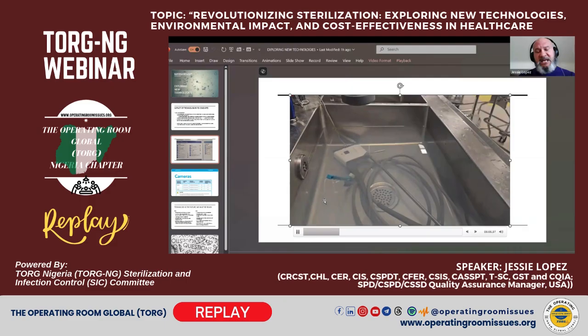Now, when we're soaking, we do set timers so that we know that the minutes are allocated. And again, I'm going to skip forward through this device, and we'll have our cleaning tools available, which are cleaning brushes to clean some of the intricate parts in there, the curves and the buttons. And then we're going to use disposable brushes to clean the hoses, the cords, the shaft of the instrument, and of course the glass in the front on the distal tip of that device.